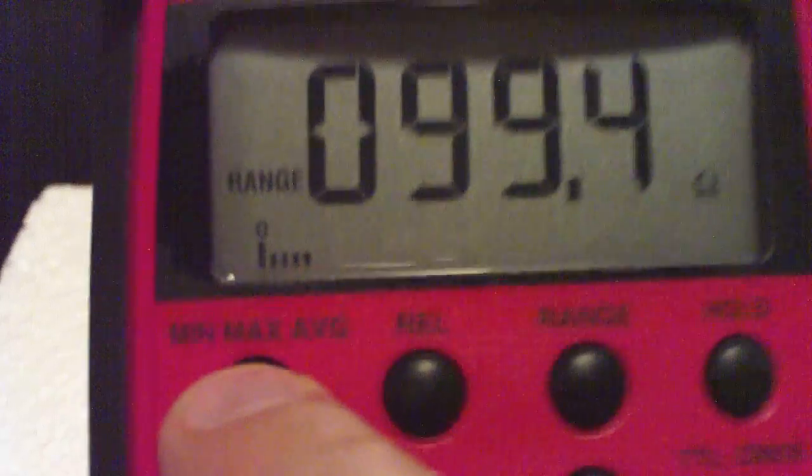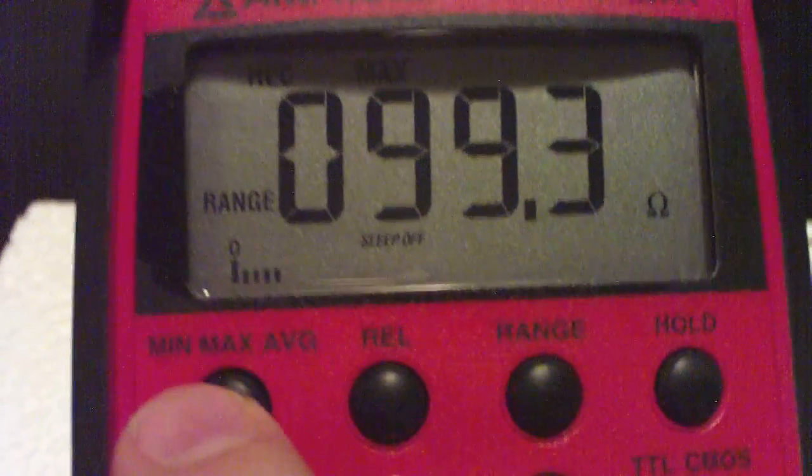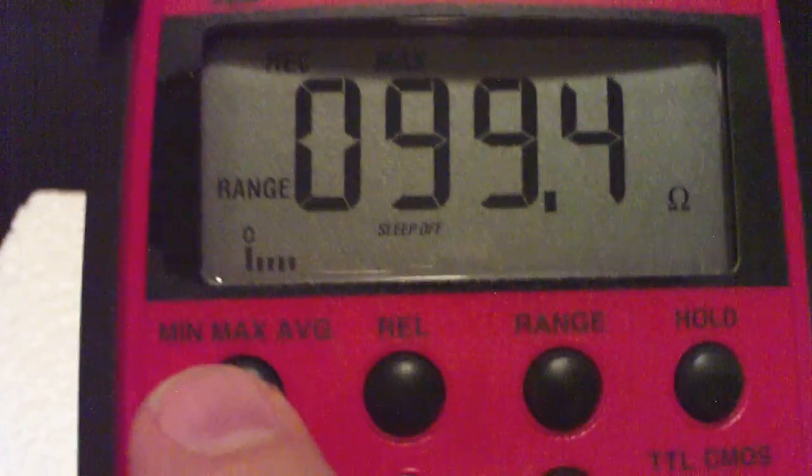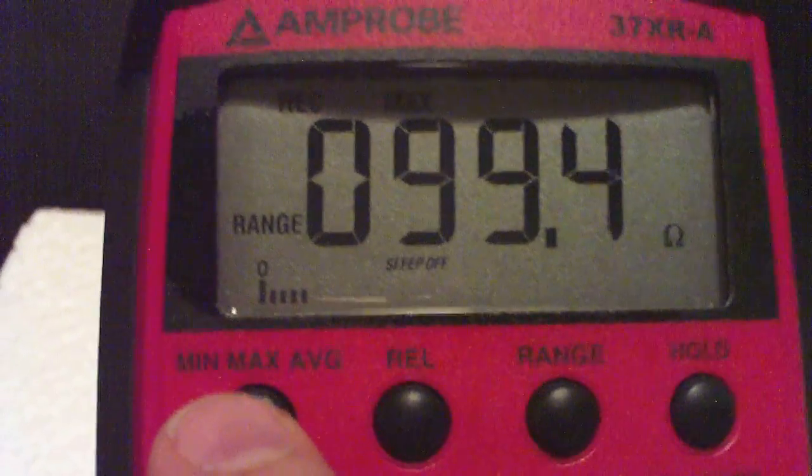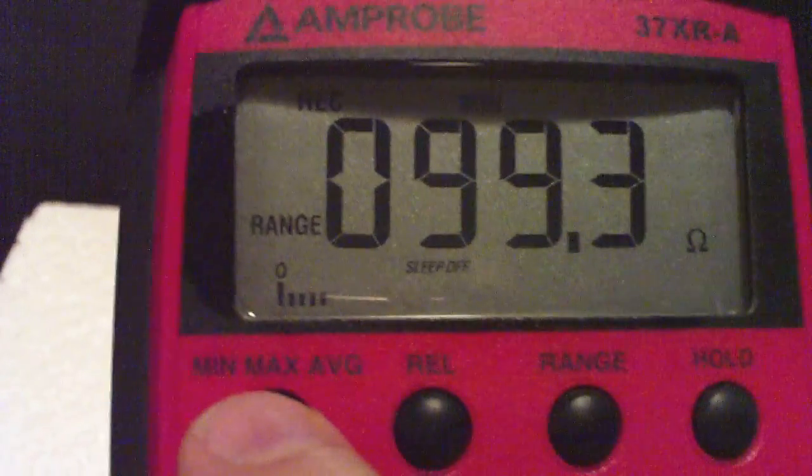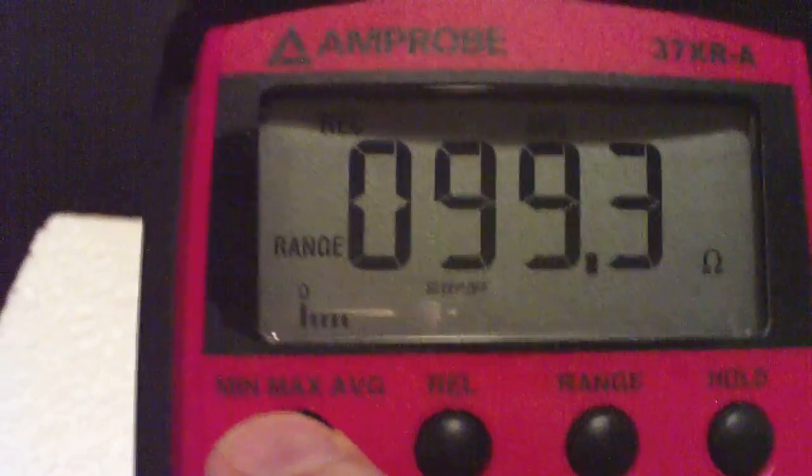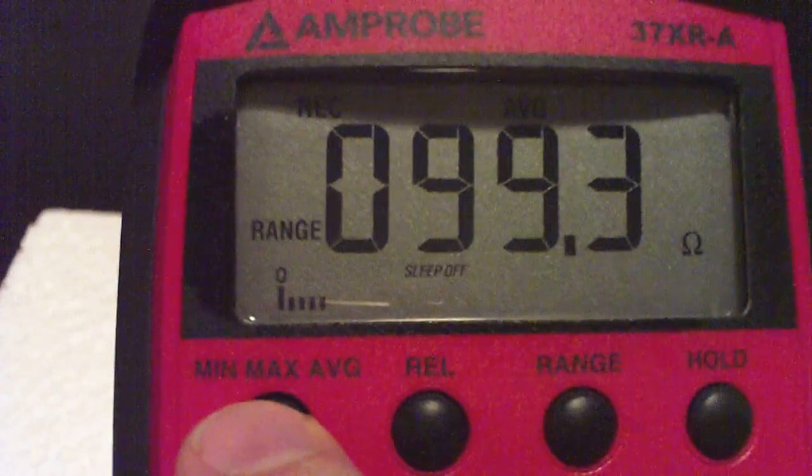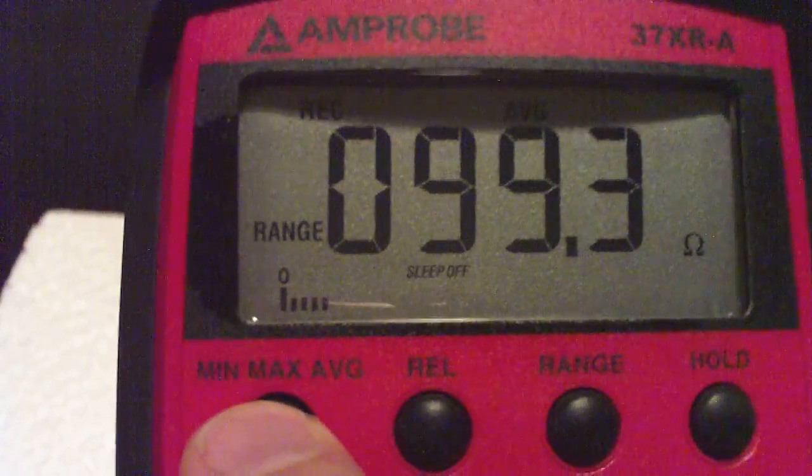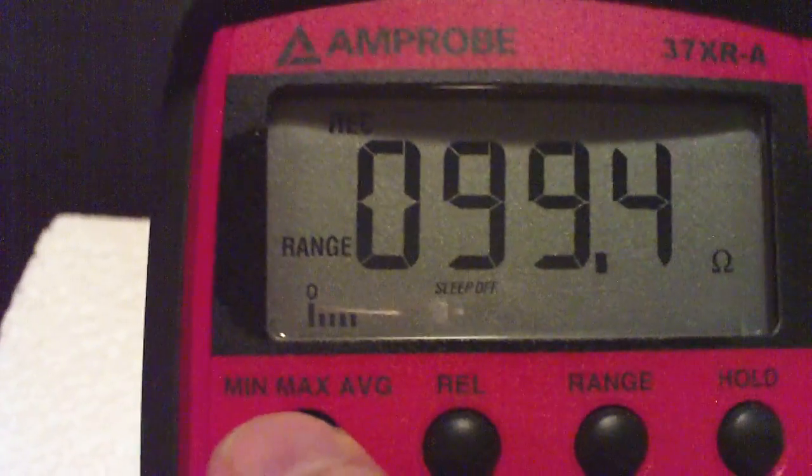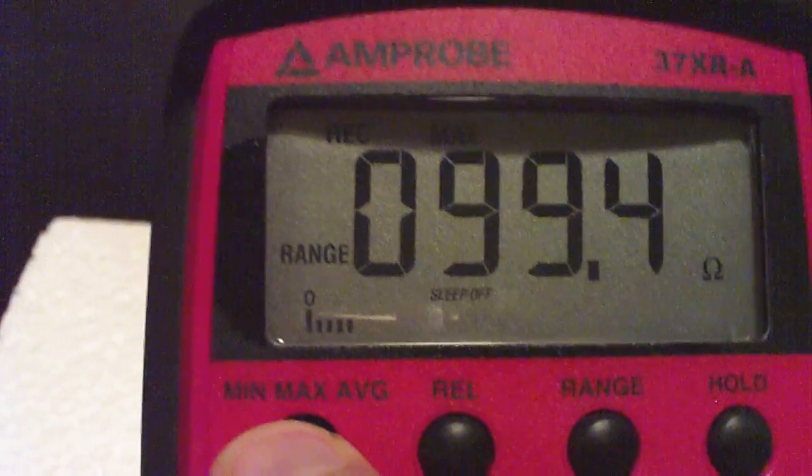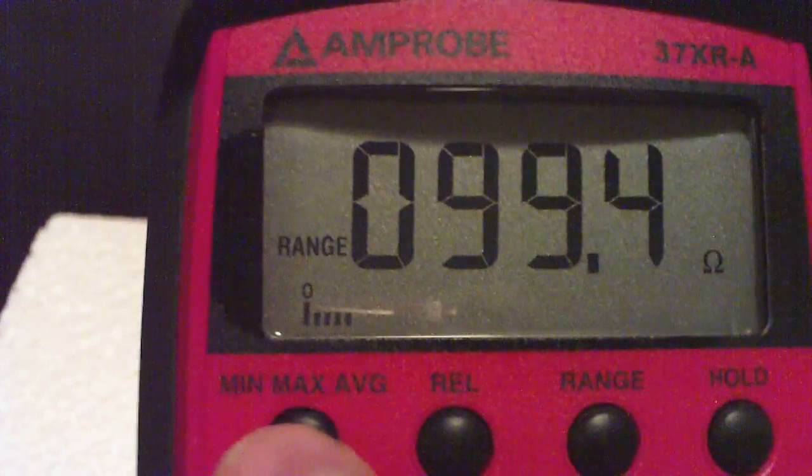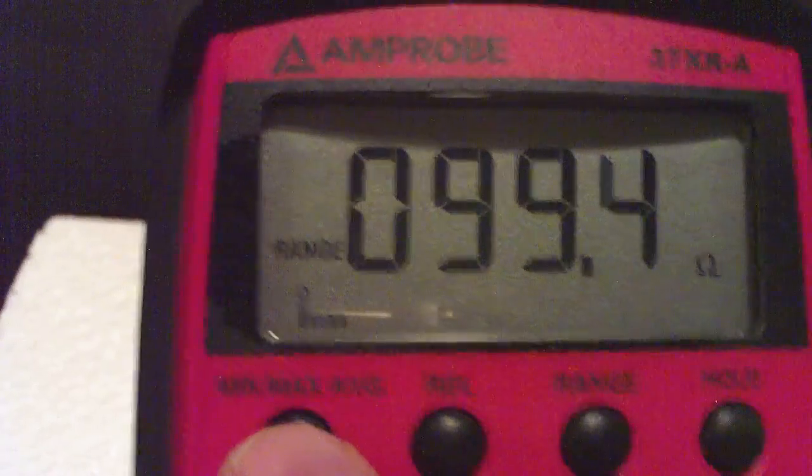Over here we have a min max button, and now it's recording data. And now it's going to hold on the maximum, or the minimum, or the average value. And if you had something changing a little bit, you might want to utilize that. If you hold this button down, it'll turn off the min max recording.